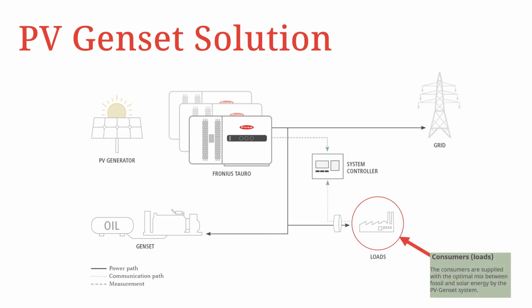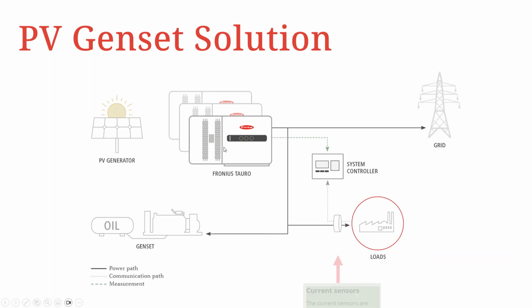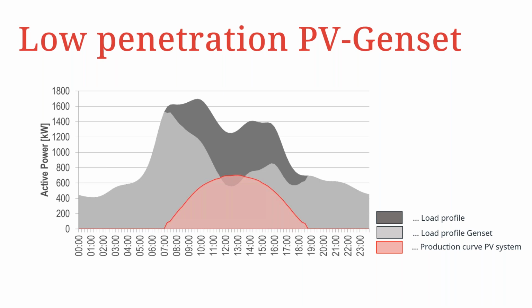And then we look at the loads that are being supplied with an optimal mix of the earlier said sources of power. Most importantly, there is a component that plays a very, very critical role: the current transformers, or the current sensors. They are attached to the PV system, and they are able to read how much current is being drawn from the load. This enables the system controller to determine how much power should be drawn from any of these sources. And then, of course, we have the grid, which in some cases for our target market might be limited or unavailable completely.